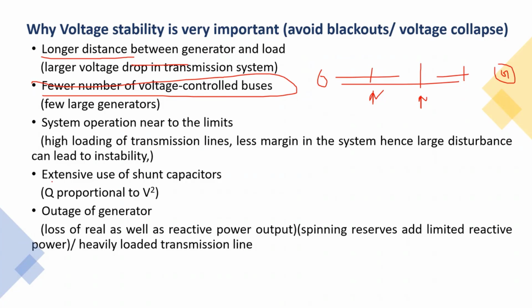Then there is another issue, which is shunt capacitors. Many times the challenge is that you have to optimally utilize the shunt capacitors. When the loading is high, you have to switch on the shunt capacitors to provide reactive power support, so that those loads can operate at unity power factor. And when the loading is low on the distribution side, you have to switch off those capacitors.